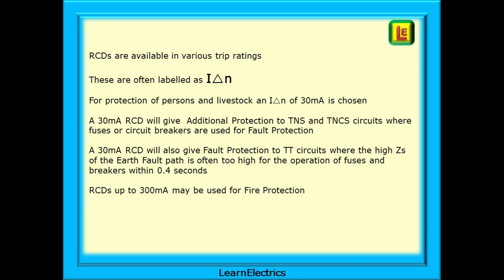RCDs are available in various trip ratings, often labelled as I-delta-N — the current difference in the neutral. For protection of persons and livestock, an I-delta-N of 30mA is chosen, and most of this video is about 30mA devices. A 30mA RCD gives additional protection to TNS and TNCS circuits, fault protection to TT circuits where high ZS of the earth fault path is often too high for fuses and breakers within 0.4 seconds, and RCDs up to 300mA may be used for fire protection.